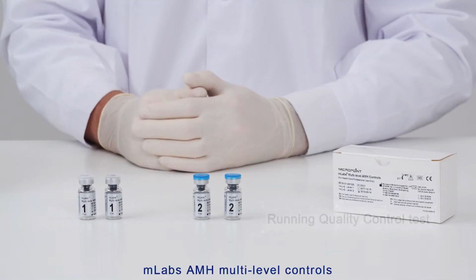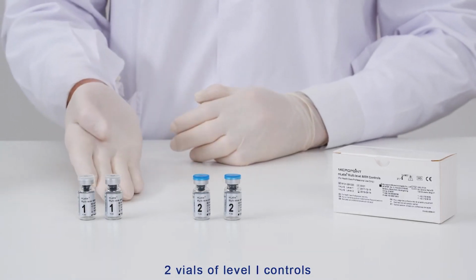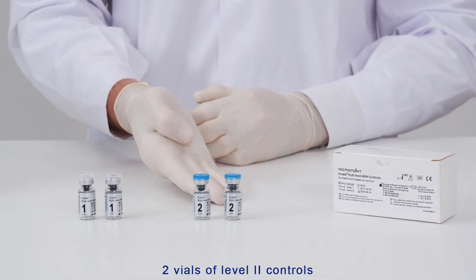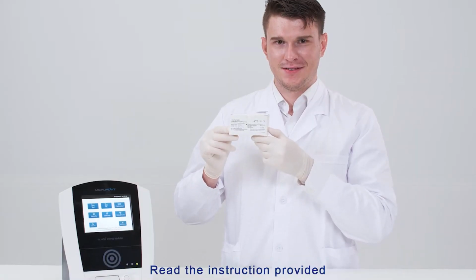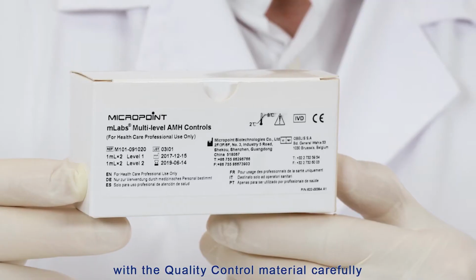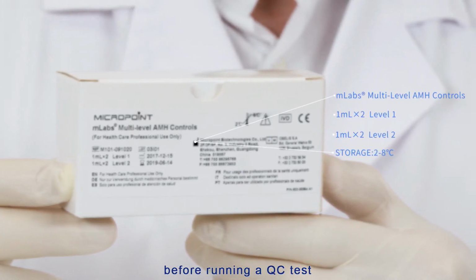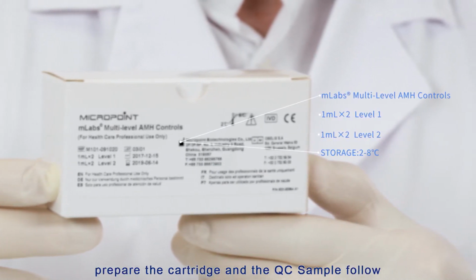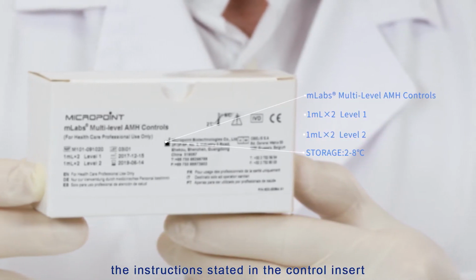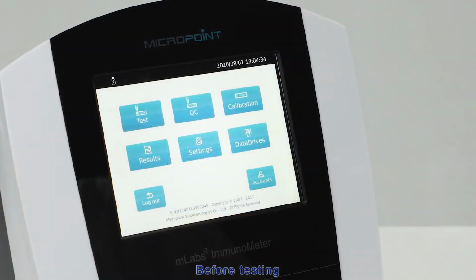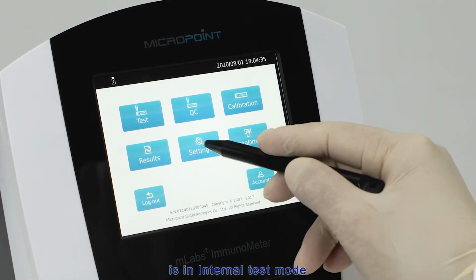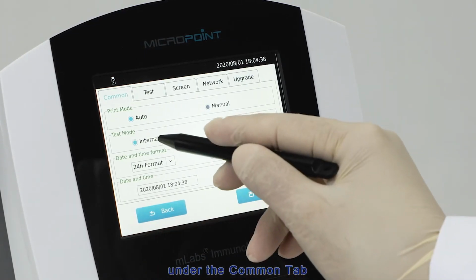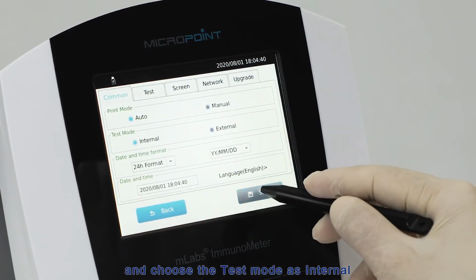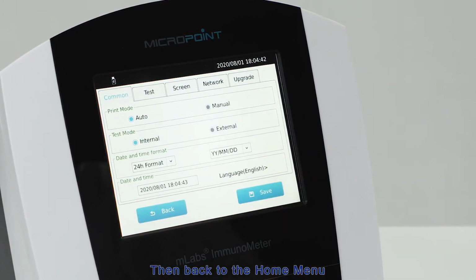mLabs AMH multi-level controls include the following materials: 2 vials of level 1 controls, 2 vials of level 2 controls, 1 product insert. Read the instruction provided with quality control material carefully before running a QC test. Prepare the cartridge and the QC sample. Follow the instructions stated in the control insert. Before testing, ensure that mLabs Immunometer setting is in internal test mode. Tap Settings on the Home menu under the Common tab and choose the test mode as internal. Then back to the Home menu.